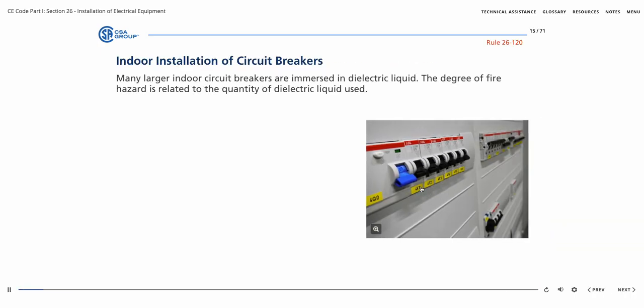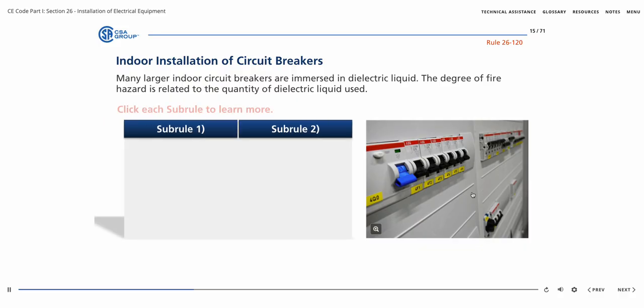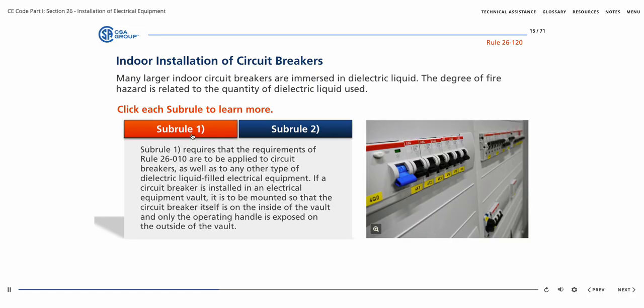Many larger indoor circuit breakers are immersed in dielectric liquid. The degree of fire hazard is related to the quantity of dielectric liquid used. Rule 26-120, Sub-Rule 1, requires that the requirements of Rule 26-010 are to be applied to circuit breakers, as well as to any other type of dielectric liquid-filled electrical equipment.